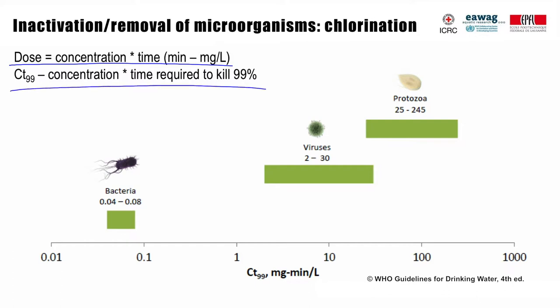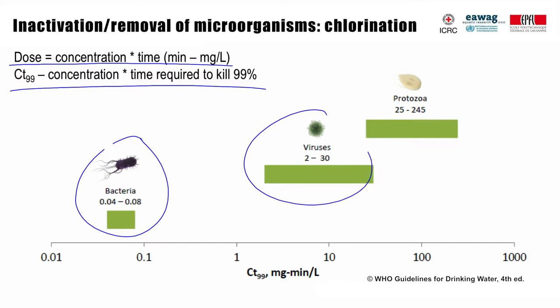CT99 means the concentration and time required to kill 99% of target microorganisms. In the case of bacteria, the CT values are low, indicating that inactivation occurs relatively fast and at low concentration. The time and concentration are considerably higher to inactivate viruses, and very high for protozoa. Cryptosporidium oocysts are resistant to chlorine, which often does not provide a sufficient level of inactivation to protect from disease. Presence of particulate matter leading to high turbidity compromises chlorination, and water must be clarified before it can be disinfected with chlorine.